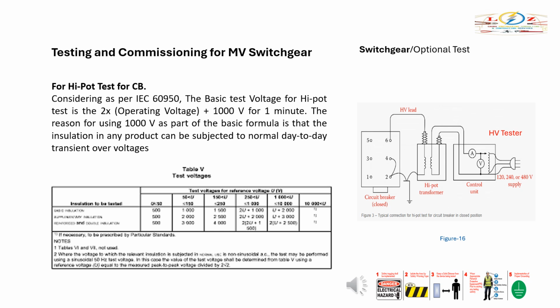Considering IEC 60950, the basic test voltage for the high pot test is 2 times the operating voltage plus 1000 volts for 1 minute at typical high pot equipment. Leakage current trip limit settings range between 0.1 and 20 milliamperes. The reason for using 1000 volts as part of the basic formula is that the insulation in any product can be subjected to normal day-to-day transient overvoltages.